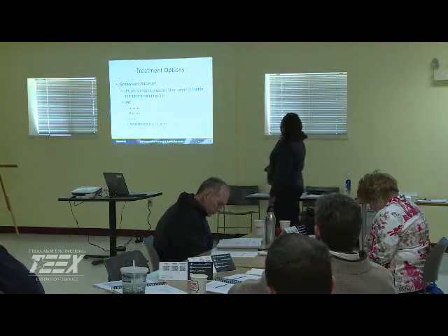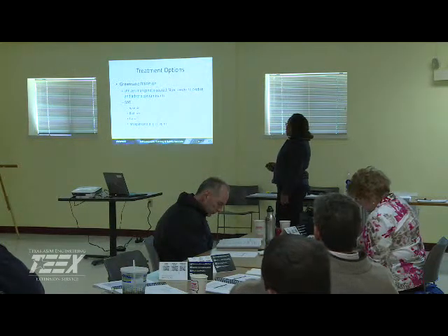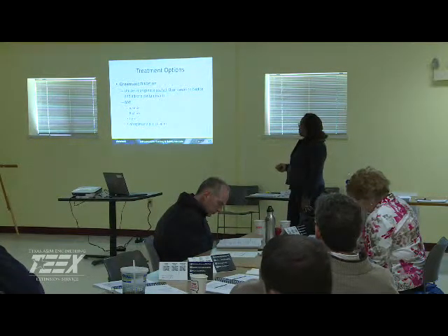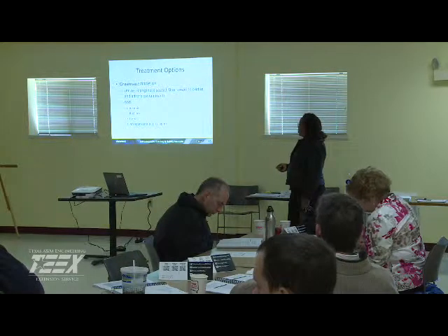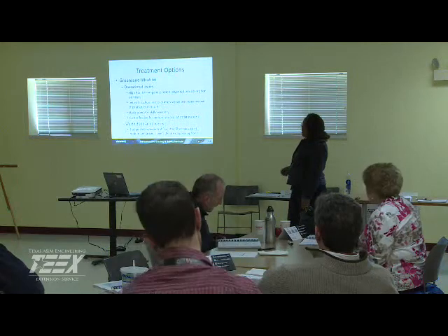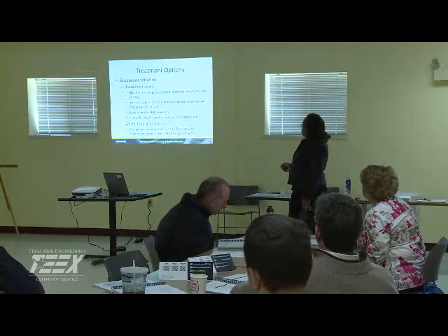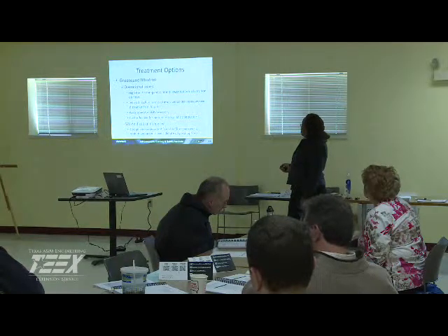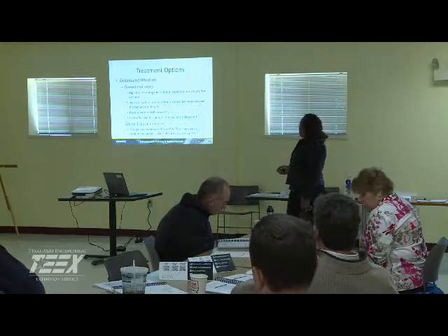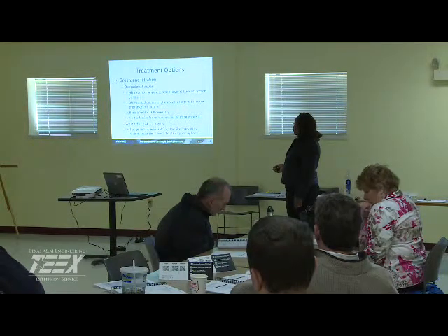Greensand filtration is another option that's available. Here we're utilizing manganese-coated filter media to oxidize and adsorb the contaminants. Again, it's good for arsenic, radium, iron, as well as manganese up to 10 parts per million. And again, they have some operational issues. pH again would be one of the dependent factors. It can be cost effective for radium removal for your small systems.